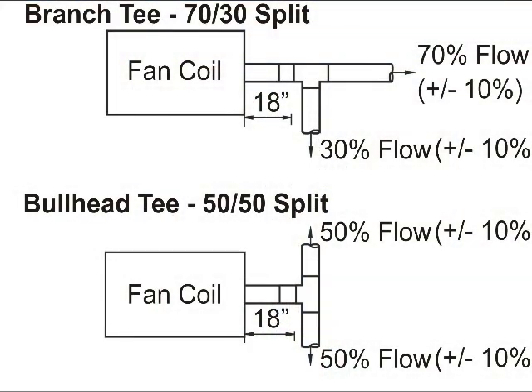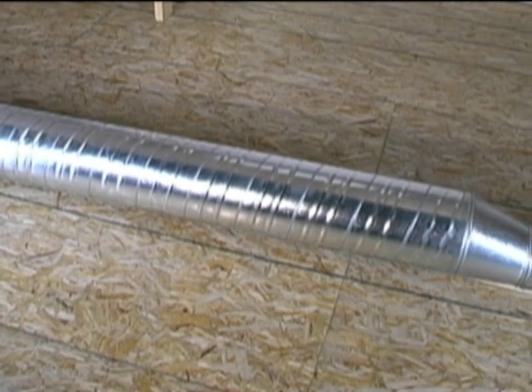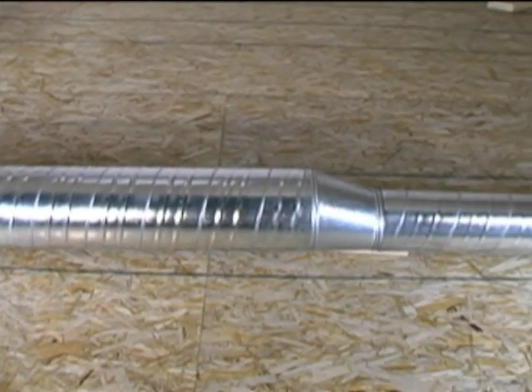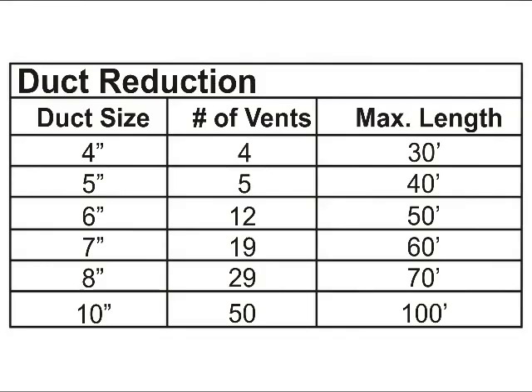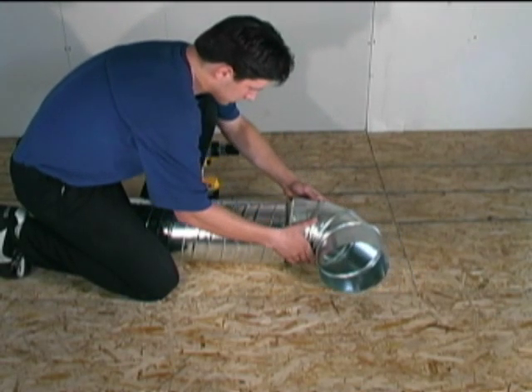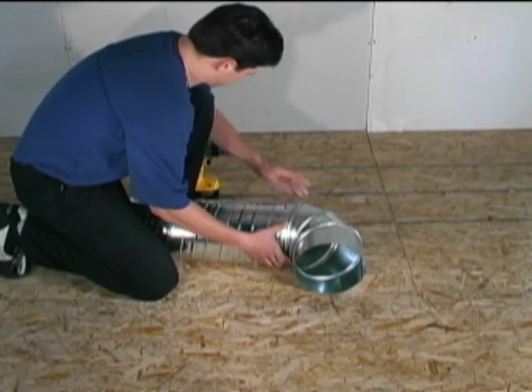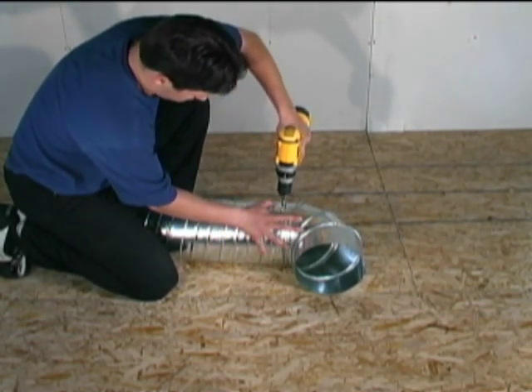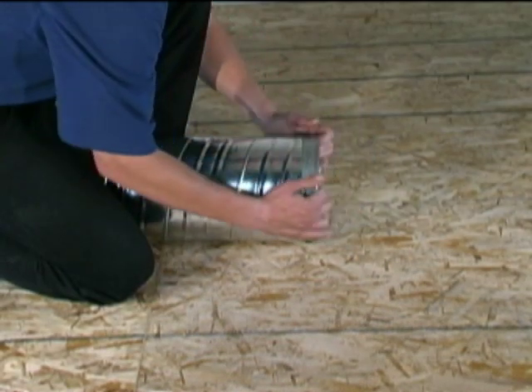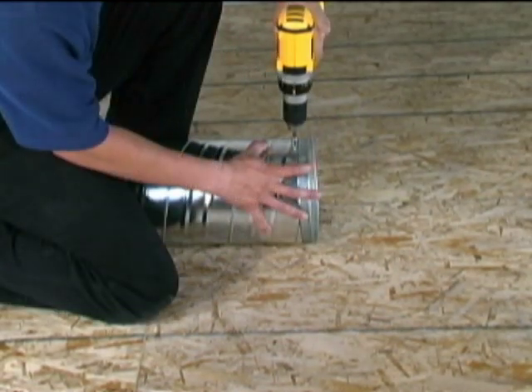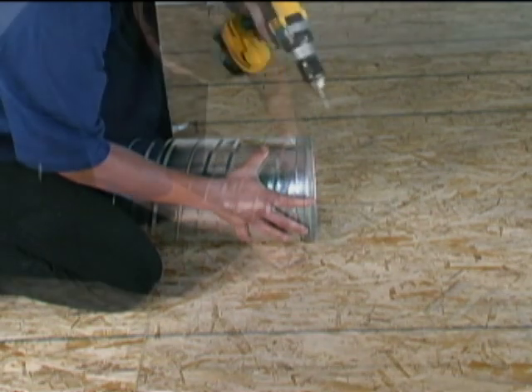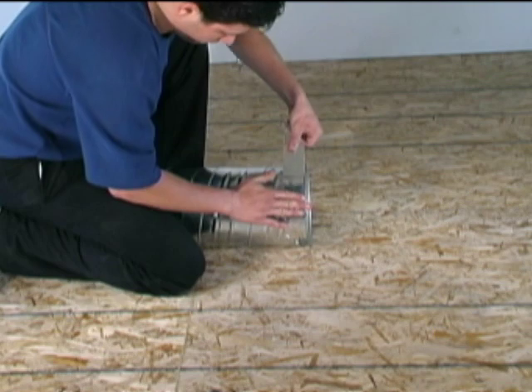For details on airflow requirements for branch or bullhead T connections, refer to the installation guide. When it is necessary to reduce the size of the main plenum, care must be taken in selecting the right number of branch outlets relative to duct size. The installation guide provides complete plenum sizing and selection tables. Typically, the main supply plenum is assembled on the floor before being suspended in place. Insert the elbow, T, or end cap into the main supply plenum and ensure a tight fit. Secure the connection using four sheet metal screws. Seal all joints to ensure an airtight connection.